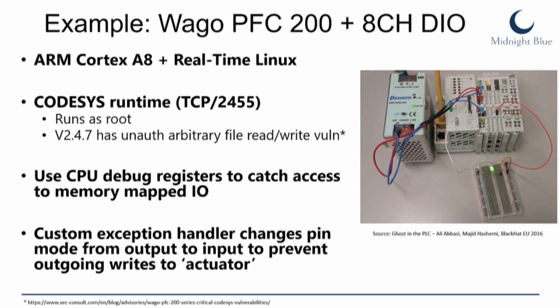Basically what we do in our attack is use the CPU debug registers to catch any access to this memory mapped I/O. Then we write a custom exception handler that gets invoked when this debug trap is triggered, and we change the pin mode, for example, from output to input. So any writes that would have been going to an actuator, like closing a valve, are now going to an input pin, and they don't actually go out.